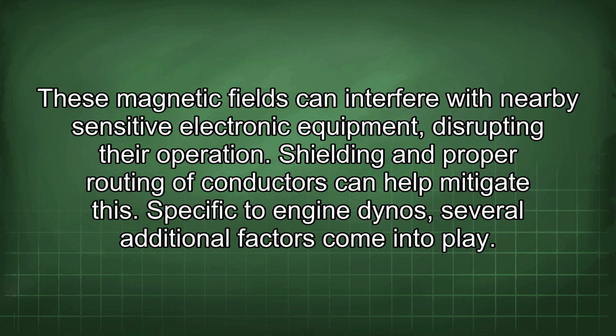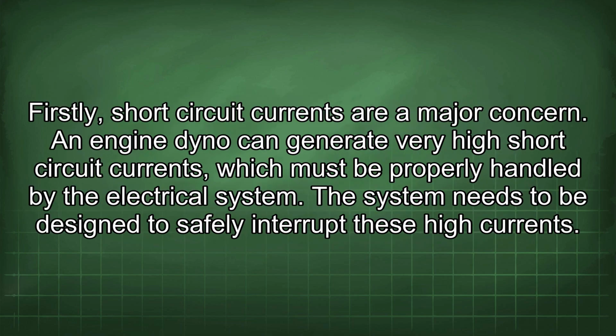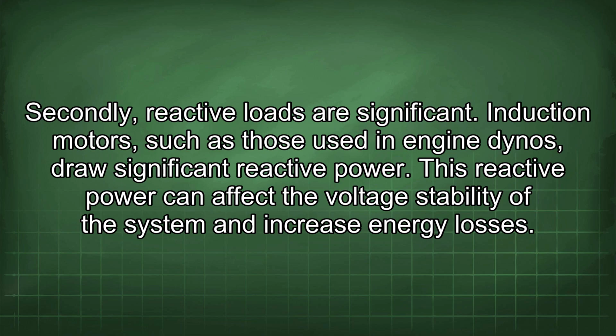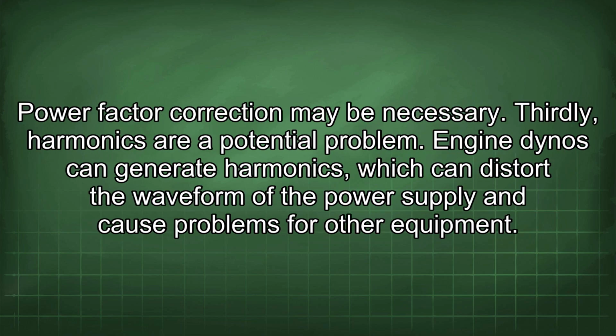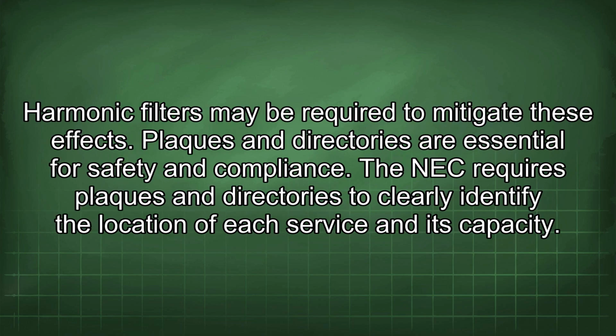Specific to engine dynos, several additional factors come into play. Firstly, short-circuit currents are a major concern. An engine dyno can generate very high short-circuit currents, which must be properly handled by the electrical system. The system needs to be designed to safely interrupt these high currents. Secondly, reactive loads are significant. Induction motors, such as those used in engine dynos, draw significant reactive power. This reactive power can affect the voltage stability of the system and increase energy losses. Power factor correction may be necessary. Thirdly, harmonics are a potential problem. Engine dynos can generate harmonics which can distort the waveform of the power supply and cause problems for other equipment. Harmonic filters may be required to mitigate these effects.